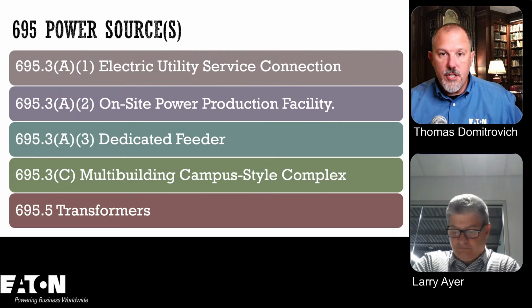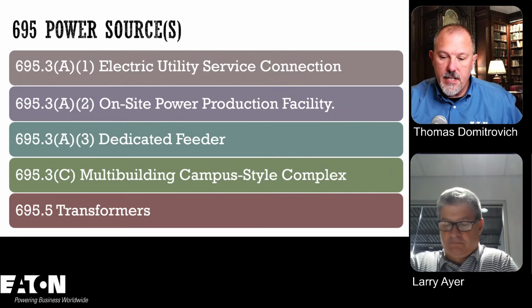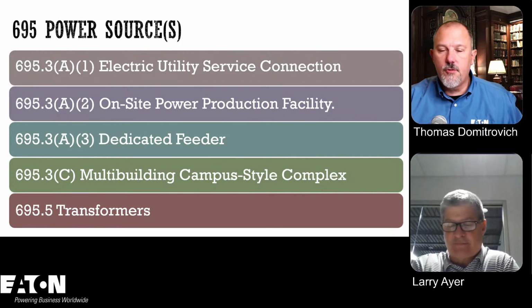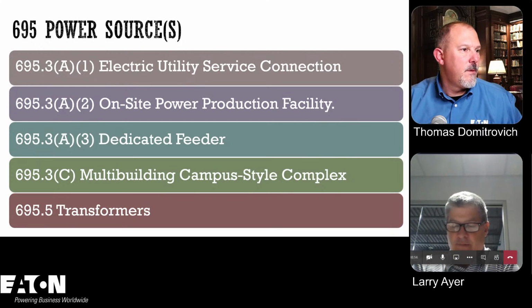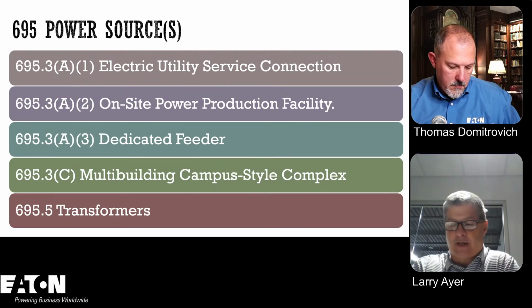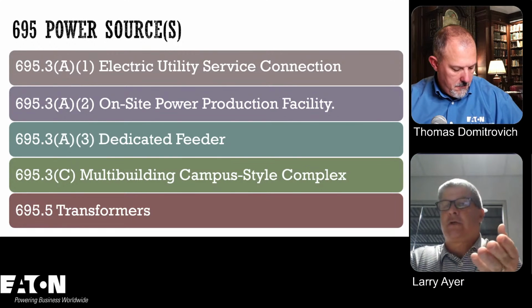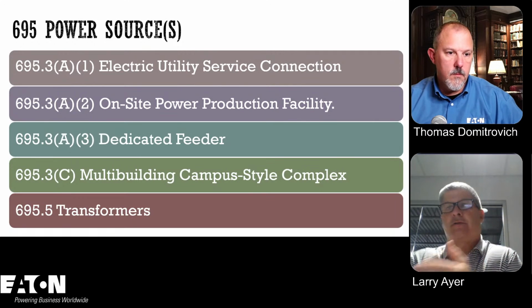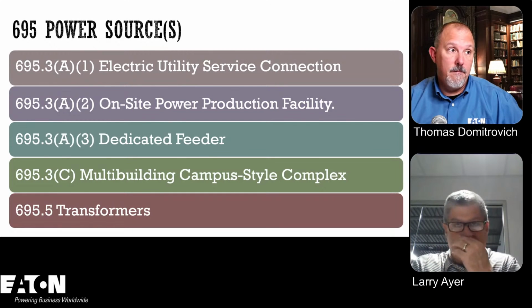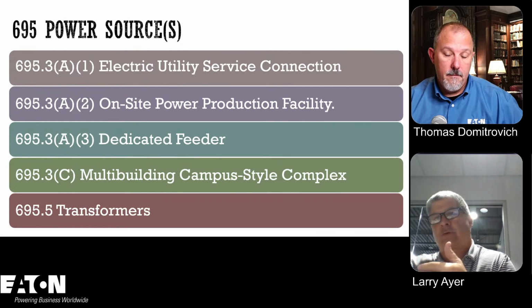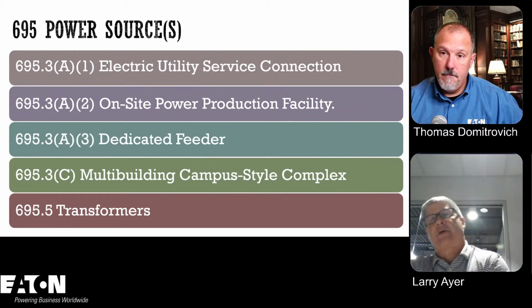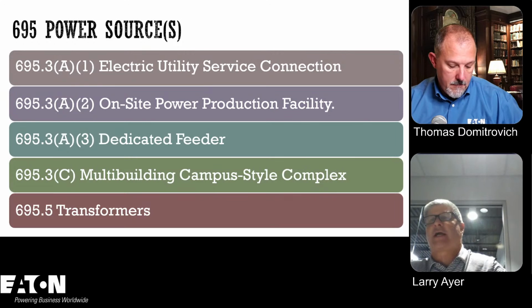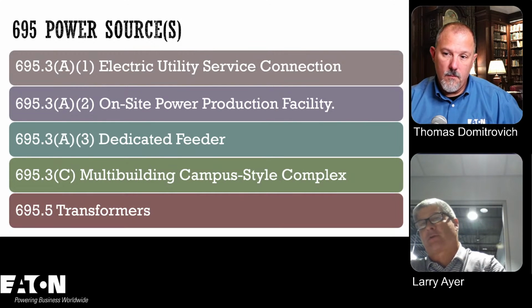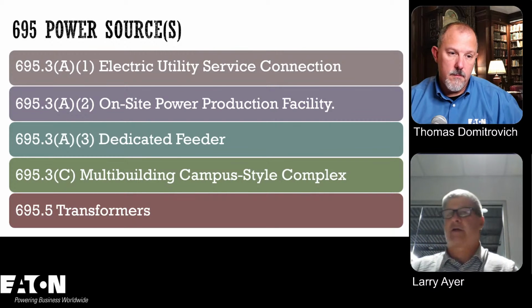I'm not sure about the voltage levels and things of that nature, but 695.5 does hit your generators. Well, 695.5, your transformers. 695.5 basically talks about putting the transformer in there. So in this case, you'd have a 13.2 disconnect going to a 13.2 to 480 step down transformer, which is going to be pretty beefy and pretty costly, and then go into a fire pump. And as we all know, maintaining and working on 13.2 is not as easy as maintaining and working on 480 or 208. So even though that's in there, I've seen people try to work with the AHJ to come up with other alternatives to put an alternate source to make sure that they comply, but maybe make maintenance and other things a little bit easier.